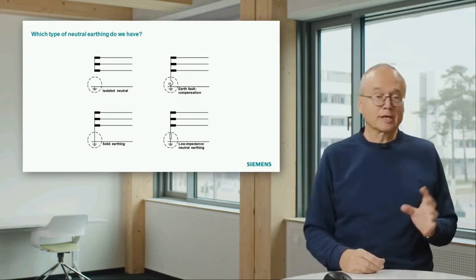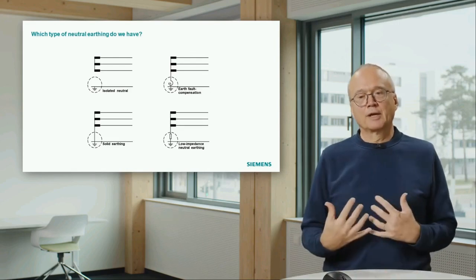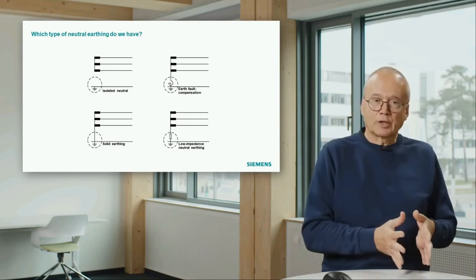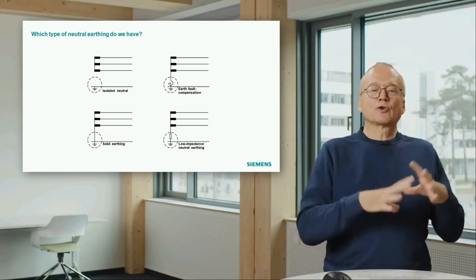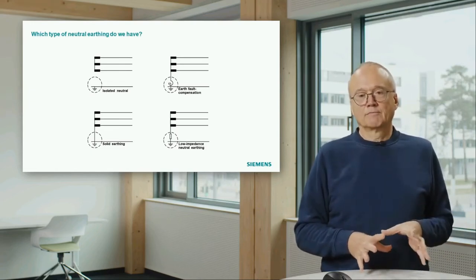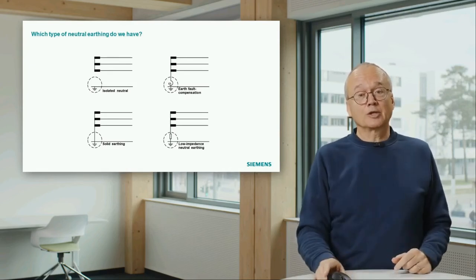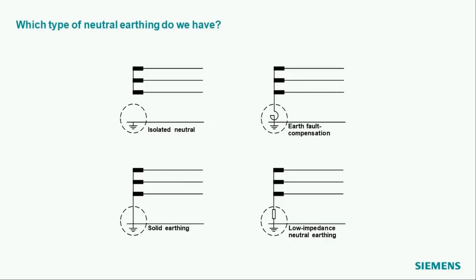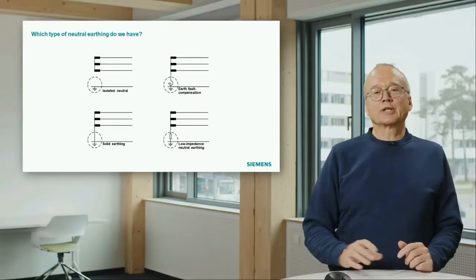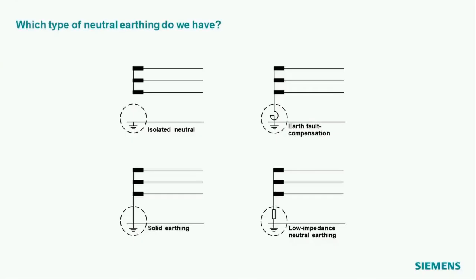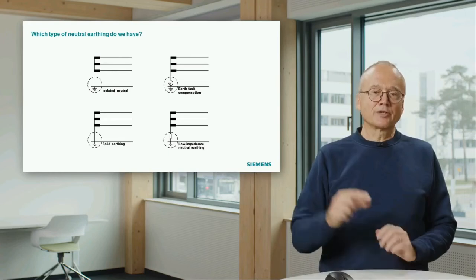And for some cases, especially in distribution systems, this is done. Because for the most probable type of fault, you then have a reduced short circuit current, which means the risk of damage, of injury of people and so on is lower. But that refers only to phase-to-ground faults. That does not influence the short circuit current in case of a phase-to-phase fault. And you can do even more things. You can put in a reactance here. And with such a reactance, you can bring down the short circuit current even to zero, or you can leave this open. That means if you have such an arrangement, a reactance here or the star point open, you have pretty low currents in case of a phase-to-ground fault.